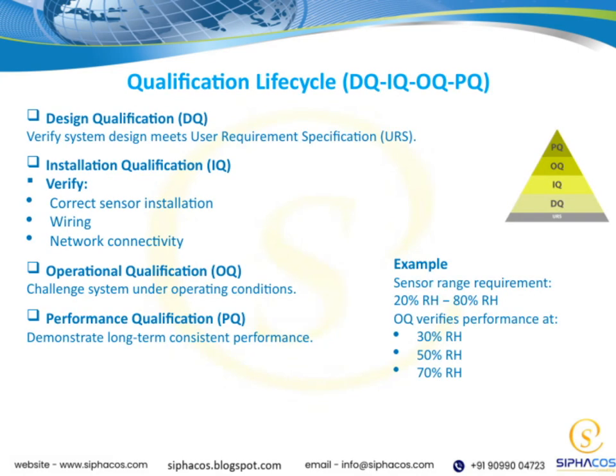Let's walk through an example of how we qualify a sensor system. The sensor needs to operate accurately between 20 and 80% relative humidity. During operational qualification, or OQ, we test performance specifically at 30, 50, and 70% humidity. The qualification process has 4 stages. First, design qualification ensures the system meets the user's requirements. Installation qualification confirms the sensor is installed correctly, with proper wiring and network setup. Then, operational qualification challenges the system under real conditions. Finally, performance qualification proves it works reliably over time.